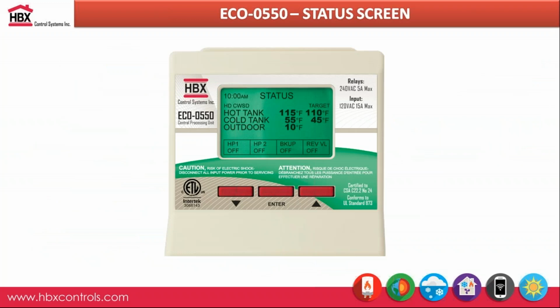Again, all your information is all on one screen. Here you can see your hot tank, cold tank, and your outdoor temperature. Any demands that are received within the controller are always going to be above hot tank or cold tank. So you're going to see HD, CD, again, heating or cooling demands. You can see if it's in a WWSD, warm weather shutdown, or a CWSD, which is obviously cold weather shutdown on there.